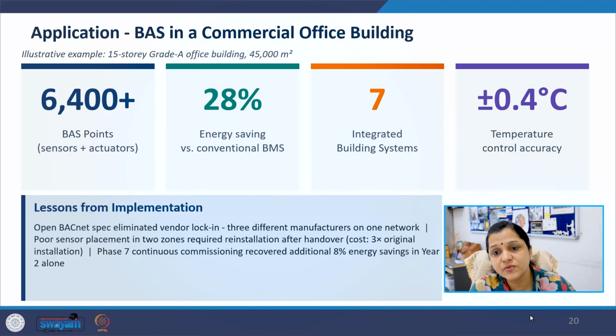The project also demonstrates several practical lessons. First, open BACnet specification allowed devices from different manufacturers to operate on the same network. Second, poor sensor placement created expensive reinstallation work after handover. And third, continuous commissioning generated additional energy saving in the second year of operation. This example shows how both technical design and operational management influence long-term building performance.